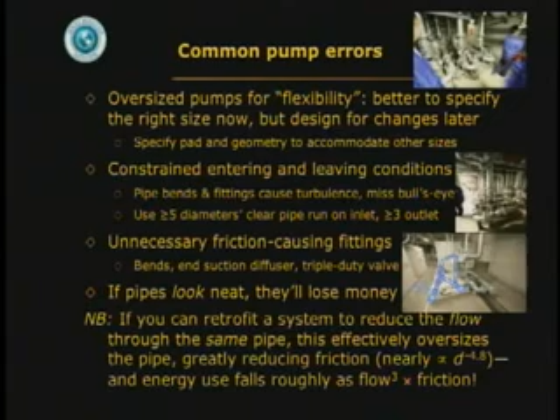And of course, if you retrofit the system with existing piping so you need less flow through the same pipes, you are typically effectively oversizing the pipe that's already there. So without having to replace the pipe, you're reducing friction as, again, nearly fifth power of diameter, and energy use falls as friction times the cube of flow. So this is a really lucrative thing to do.